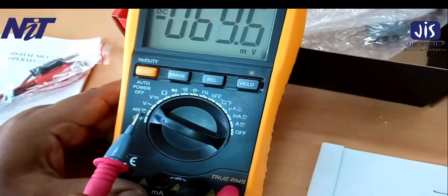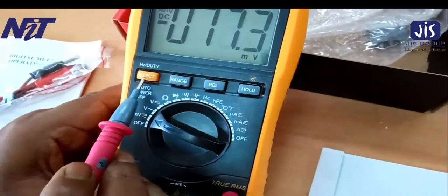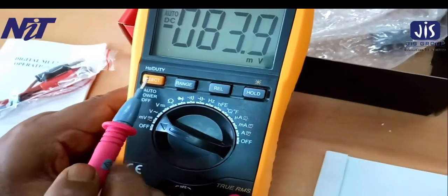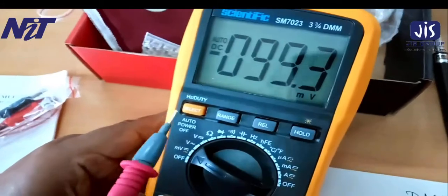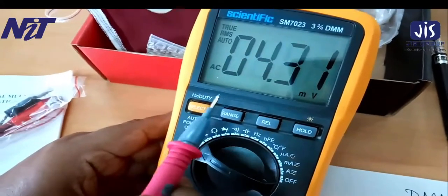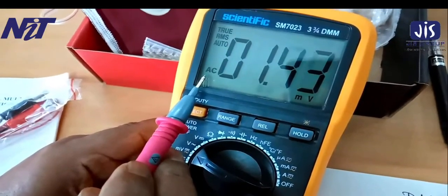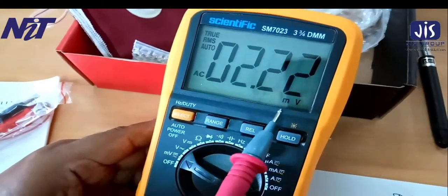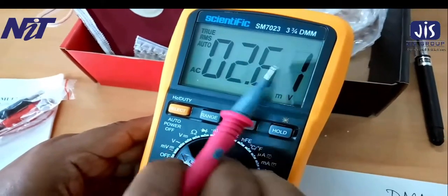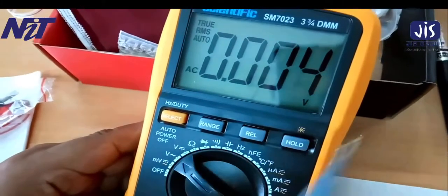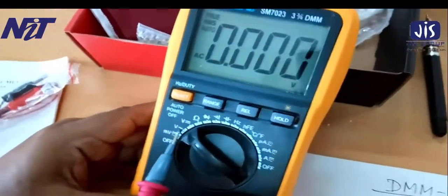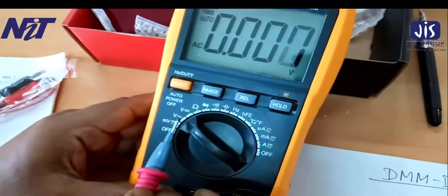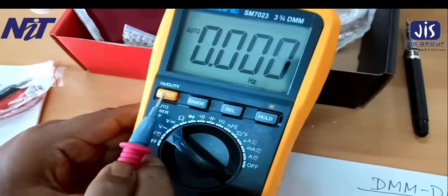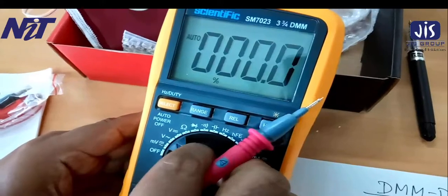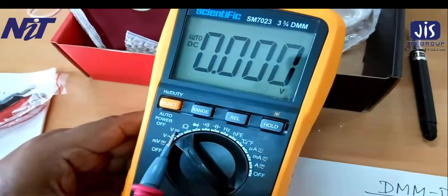And then how will it be selected? You will select this yellow select button. Normally it is in DC mode, but if you select this yellow button, then it will convert into AC millivolt mode. Okay. Then accordingly, if you go up, this is your voltage AC mode. This is dedicated only for AC. There is no option for selecting further one. And this is volts DC.